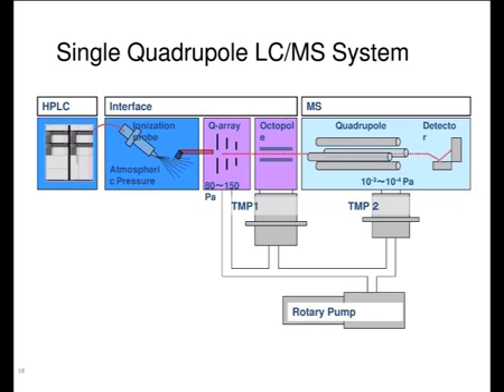What generally happens when a compound gets ionized is that it enters here, the desolvation line, where the compound enters the mass spectrometer. All of this is under vacuum; we are giving primary, secondary and tertiary vacuum. Generally for the low vacuum we use a rotary pump, and for the high vacuum we use a turbomolecular pump, which can reach a vacuum of up to 10⁻⁴ Pascal. Then ions enter the ion guides. What is their main function? To focus the ions in the same direction. It avoids the loss of ions. If ions get lost here, what happens? The total intensity, or sensitivity, will decrease. Therefore, most vendors are focusing on the development of these ion guides, so that more and more ions get focused and there is no loss of ions.